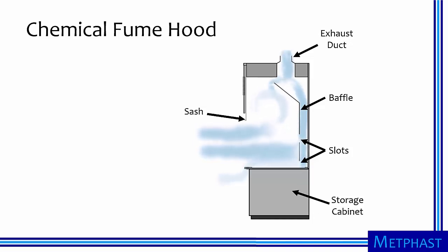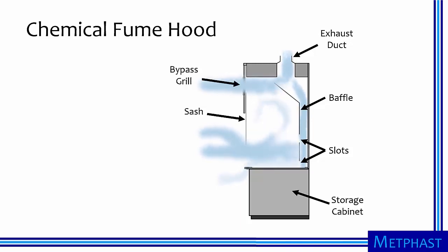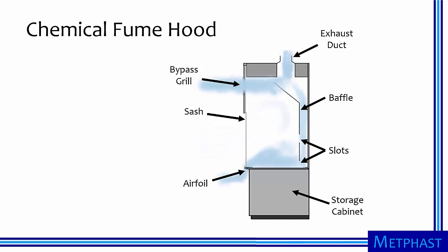When the sash is fully up, most of the air enters through the hood face. When in the middle position, some air passes through a bypass grill, the hood face, and an airfoil. Finally, when the sash is in the lowest position, air enters the hood from the bypass grill and airfoil only. These different arrangements facilitate good capture for a range of different situations.